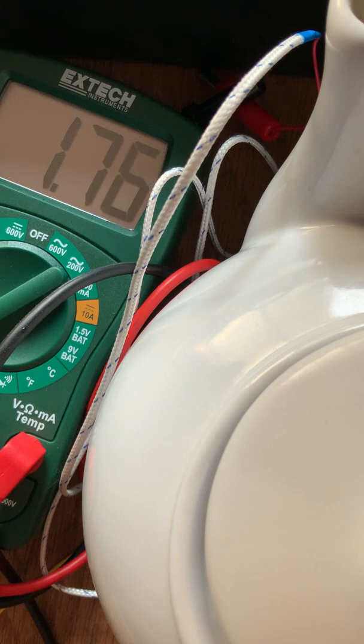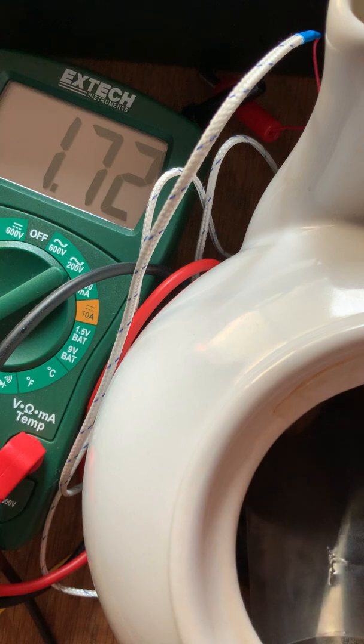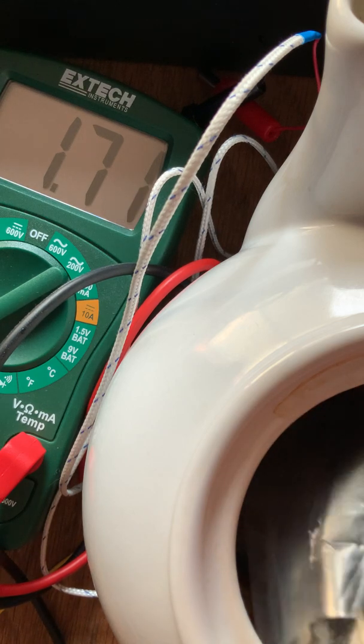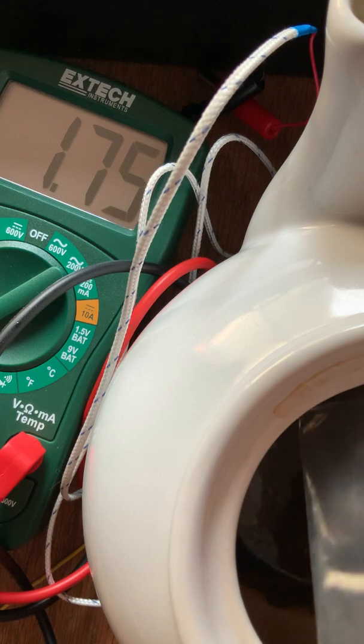And then what I'm going to do is put my temperature sensor in there. Might even go a little bit lower than that in terms of the resistance, but it's close to 1.75 kilo-ohms. Oh, 1.74. But you can see it's slowing down the rate at which it's changing. So it's going to reach a stable point pretty soon. It won't just keep going down. Maybe more like 1.7. Okay, I saw it go down to 1.71.